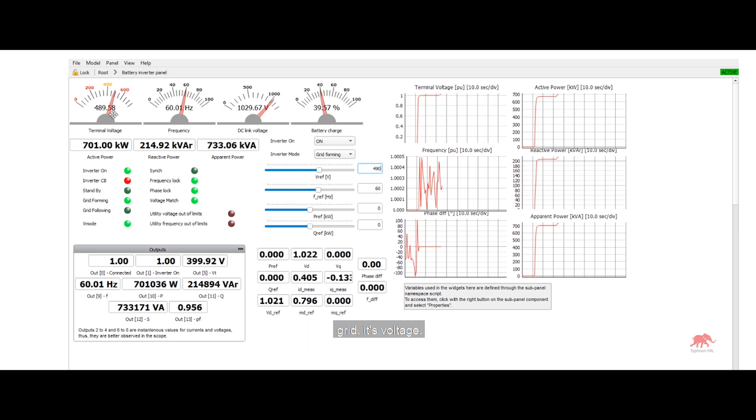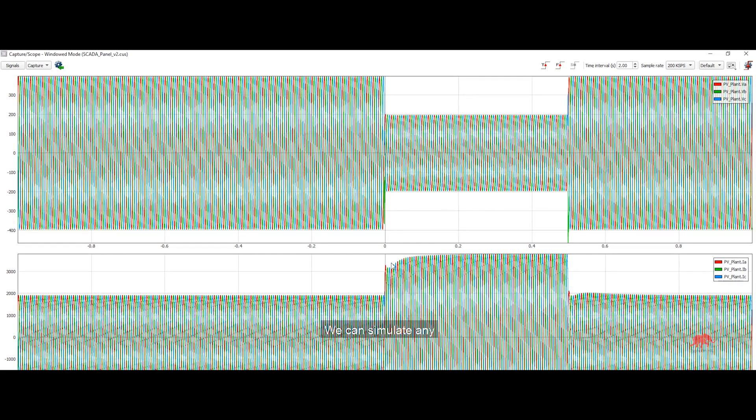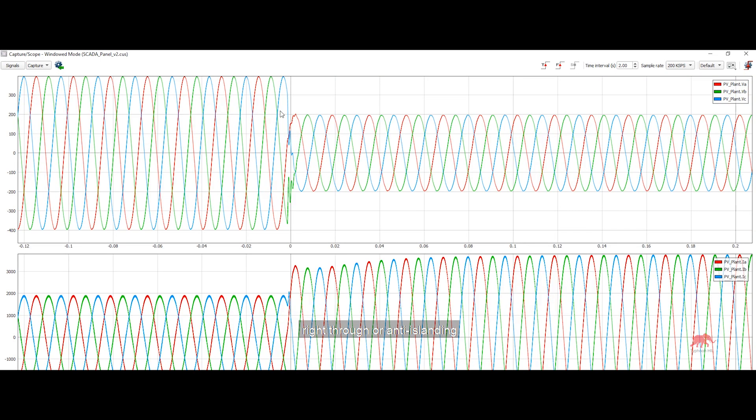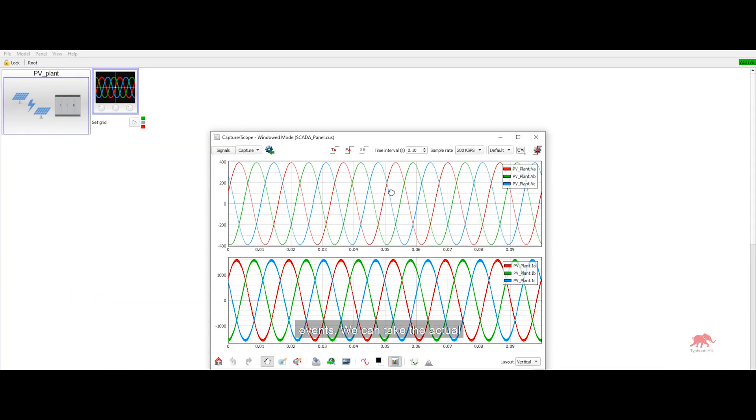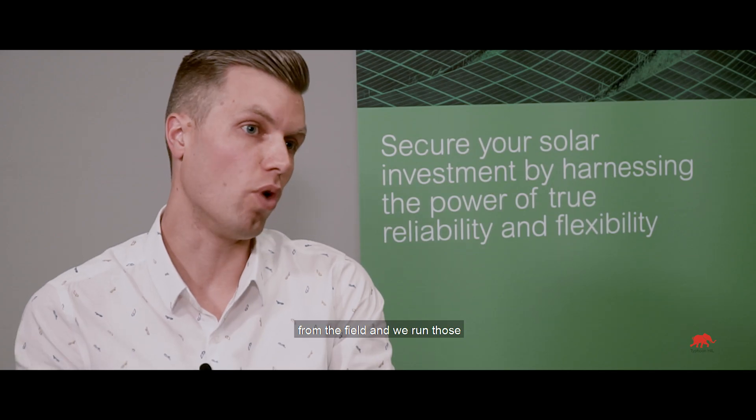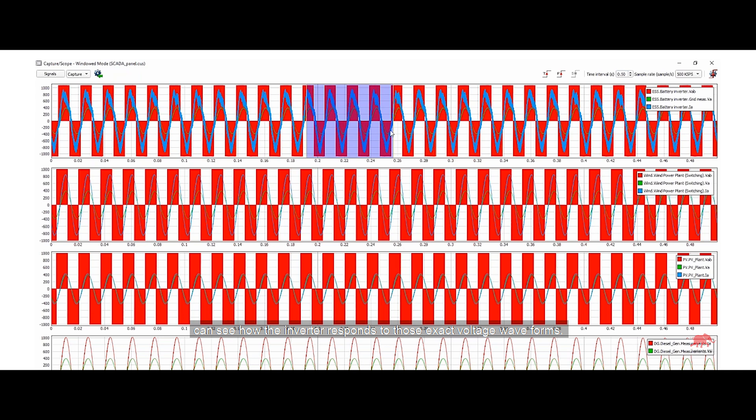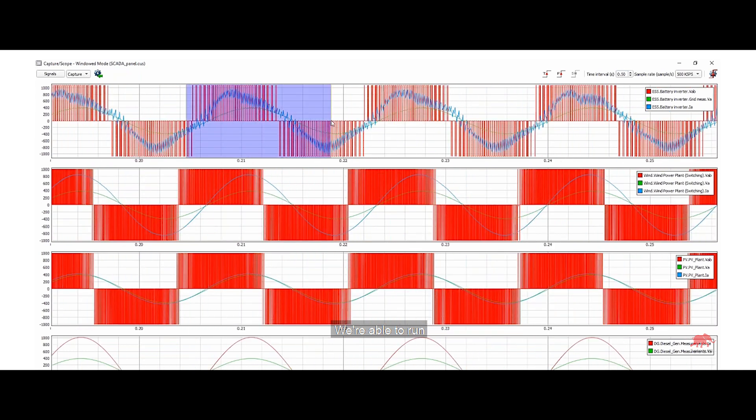its voltage, we can simulate any disturbance we want like low voltage ride through or anti-islanding events. And we can take the actual measured voltage waveforms from the field and we run those in Typhoon HIL. And we can see how the inverter responds to those exact voltage waveforms.